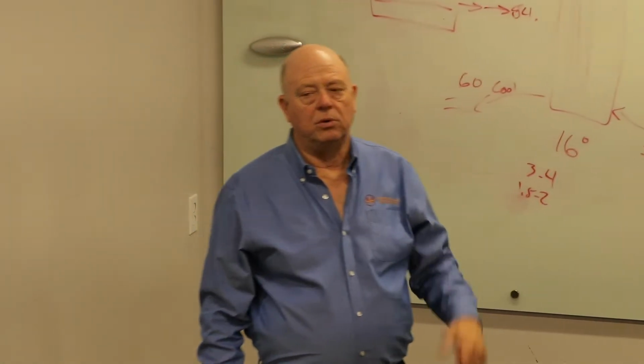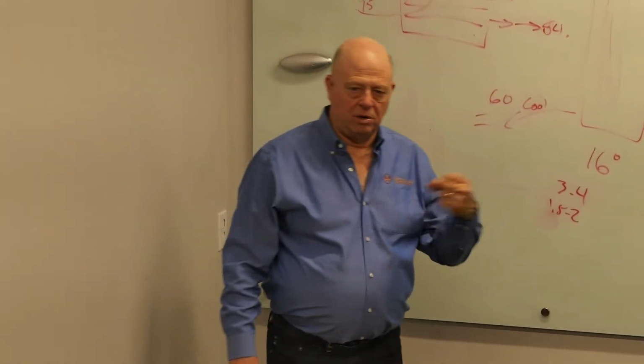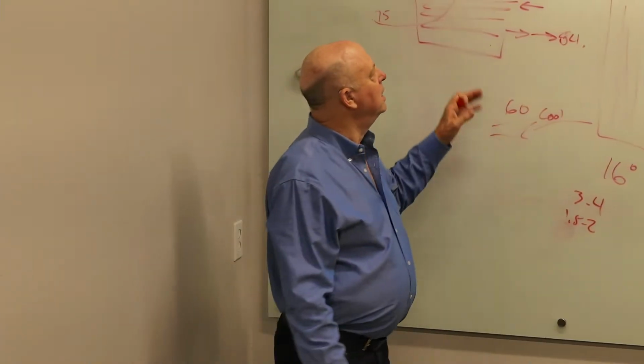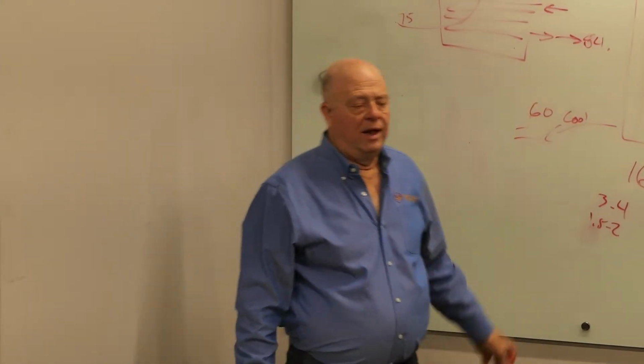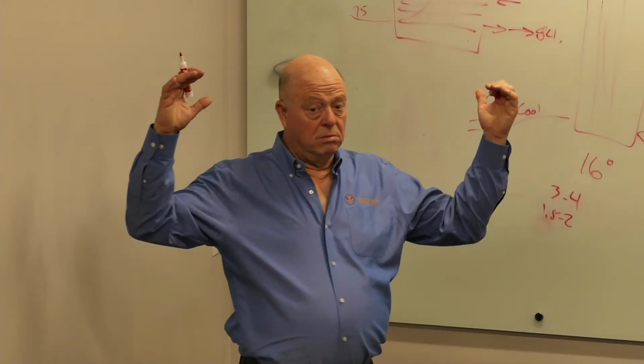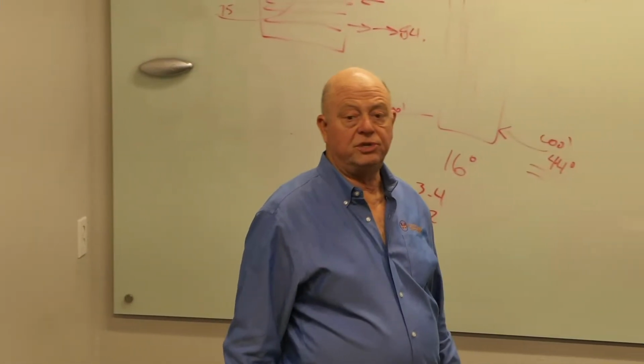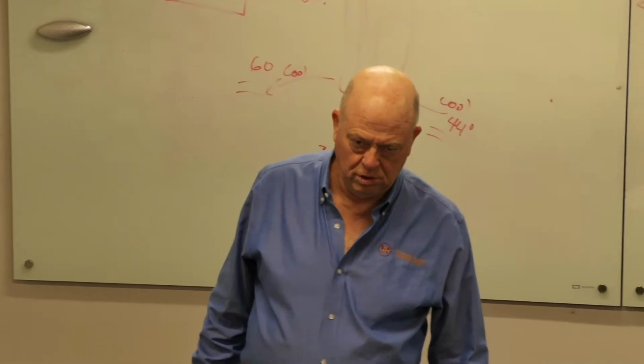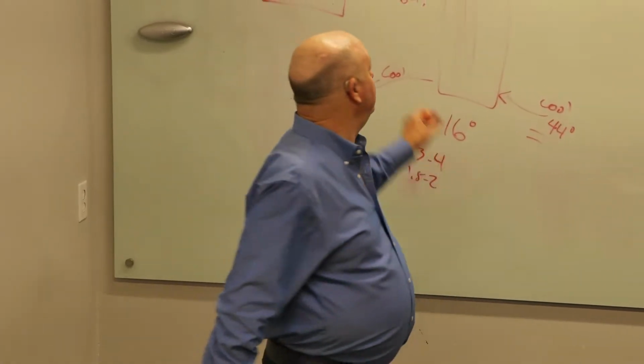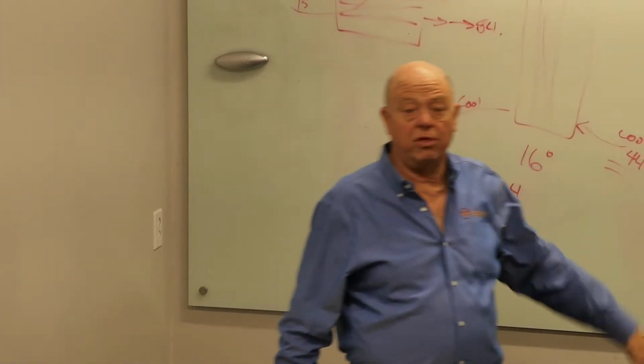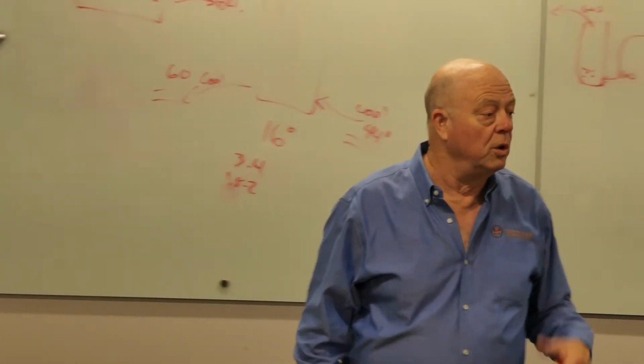It's the rare fluid cooler that will make a 9 degree approach. You're probably looking at a little over 10 somewhere. So the open tower, you might be able to get a 6 degree approach, maybe 5 degree approach, because you don't have this extra heat exchanger to screw around with and have losses in.